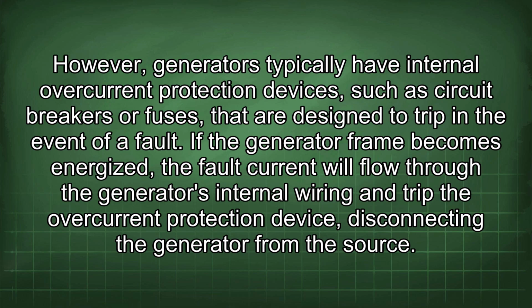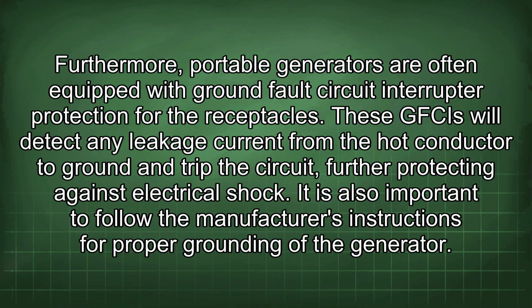If the generator frame becomes energized, the fault current will flow through the generator's internal wiring and trip the overcurrent protection device, disconnecting the generator from the source. Furthermore, portable generators are often equipped with ground fault circuit interrupter protection for the receptacles. These GFCIs will detect any leakage of current from the hot conductor to ground and trip the circuit, further protecting against electrical shock.